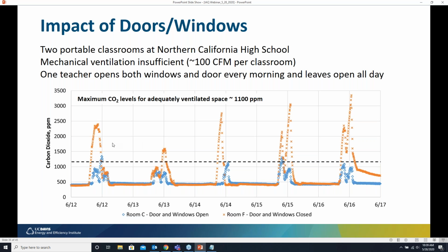In comparison, there was another teacher who always had the windows closed, and most often the door was closed. You can see that room's CO2 levels were quite high, over 3,000 at times. Both of these classrooms had a little bit of mechanical ventilation, about 100 CFM, but it was clearly insufficient. And this was a high school with fairly large classes, more than 30 students per class. So this can work, but it requires a dedicated teacher to be opening these doors and windows, and then obviously all the other concerns that I mentioned previously.